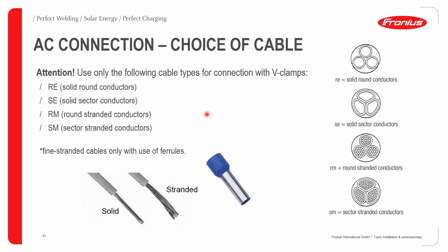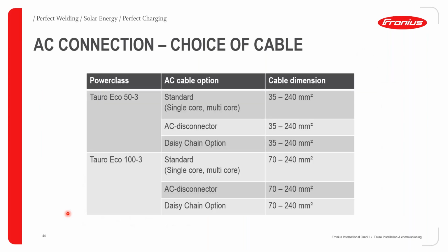For your AC connection, you have to choose the specific cables. Again, attention: use only the following cable types for connection with V-clamps. That's very important. The first one is an RE, solid round conductor. This is what a solid round conductor looks like. The second one is an SE, solid sector conductors. Again, this is what a solid sector conductor looks like. The third one is the RM, round stranded conductors. That's an example of round stranded conductors. Then you have SM, sector stranded conductors. So please make sure that you use one of these four AC cables with the V-clamps. Again, this is a real-life image of the solid versus stranded cable types.